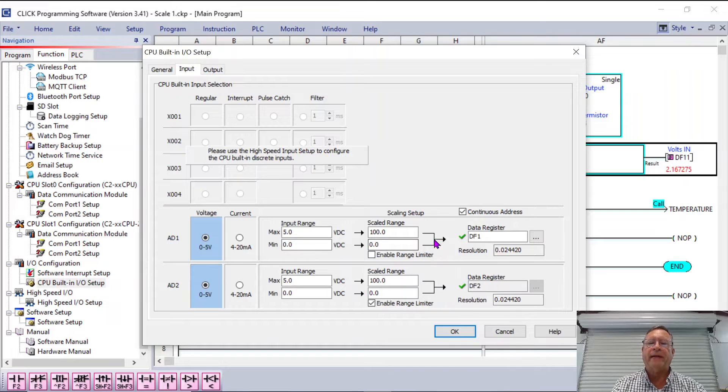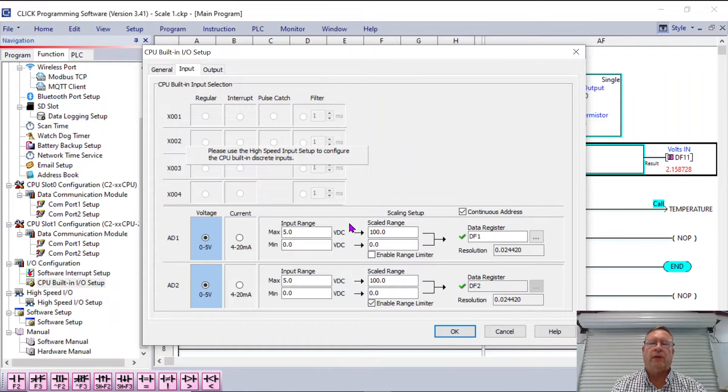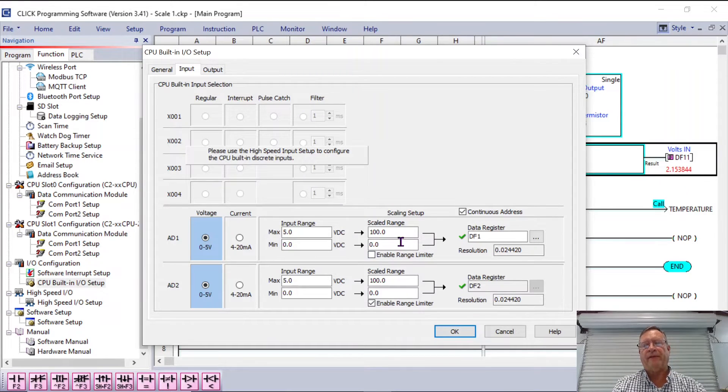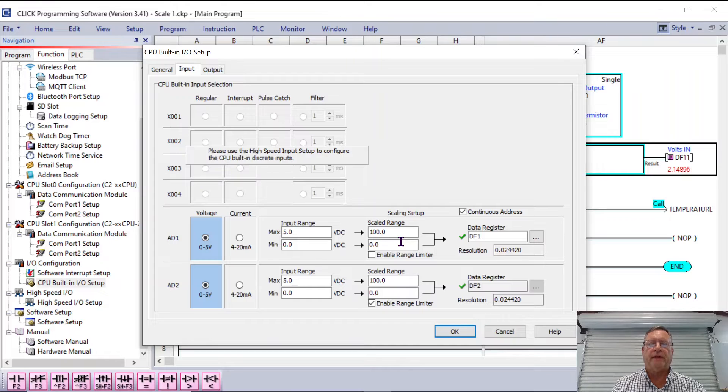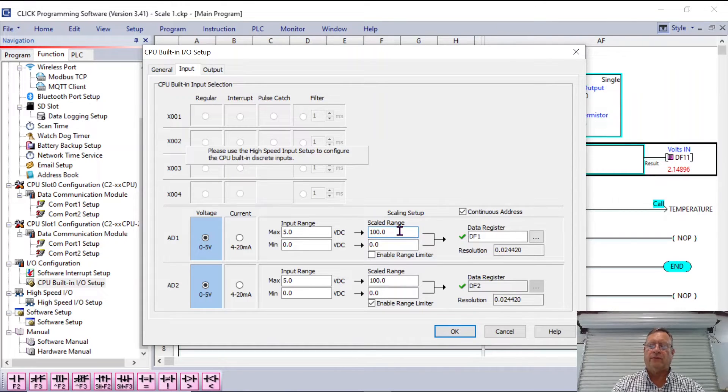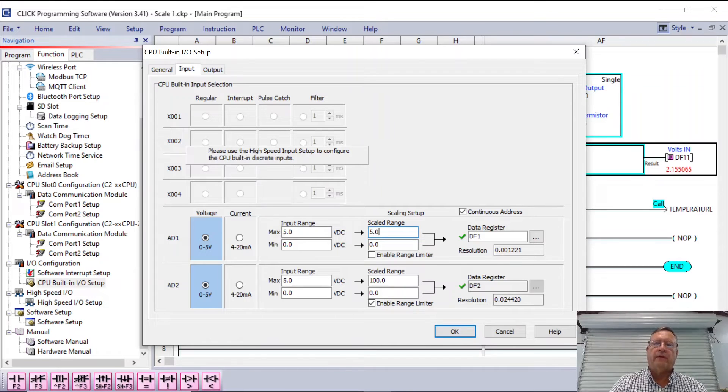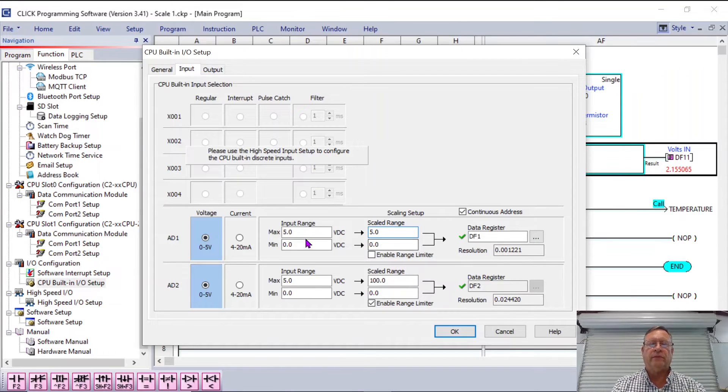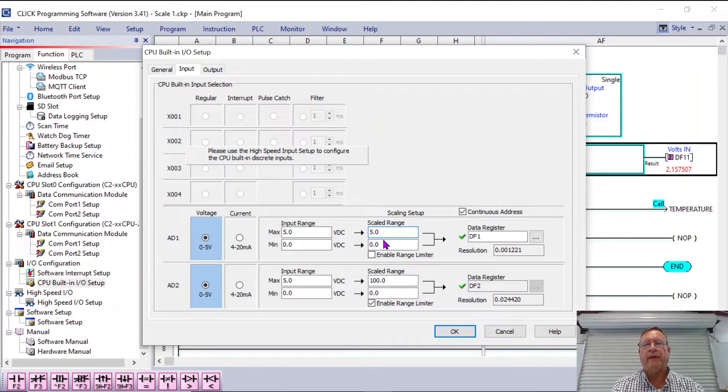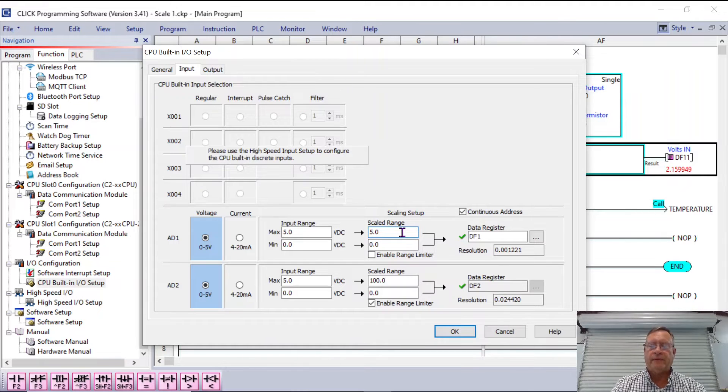But what I can change is the scaled range. Right now, the scaled range by default is zero to 100%. I could have made this 0 to 5.0, just like this over here. And that would have corrected my scaling problem. But let me take it back right now for a moment.